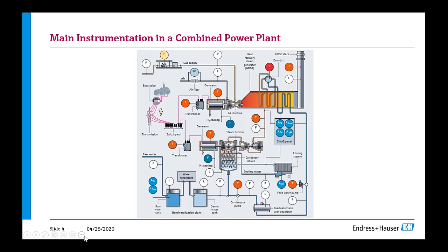So here you see the main instrumentation in a combined cycle power plant. We see that you have a lot of instrumentation like flow, level, pressure and temperature all over the place. So for instance, here at the HRSG, at the steam drums, you have some important level measurements. You've got a lot of analytical measurements because the quality of the water and the steam is of high importance. It's important quality that Endress Hauser knows to measure.